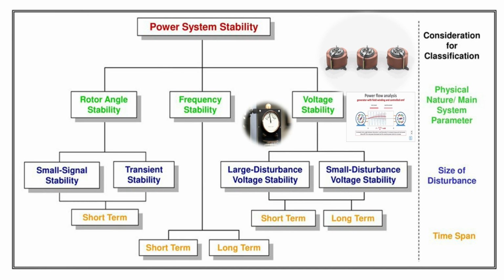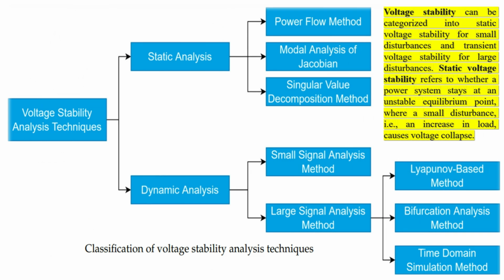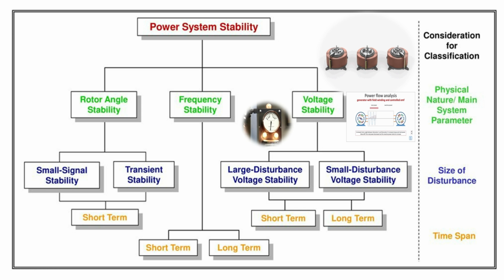Voltage stability can be categorized into static voltage stability for small disturbances and transient voltage stability for large disturbances. Static voltage stability refers to whether a power system stays at an unstable equilibrium point, or whether a small disturbance, i.e., an increase in load, causes voltage collapse. For traditional power systems, static voltage stability is determined by the active power transmission and the related voltage drop on the AC transmission line. However, for high VRE penetrated power systems, its static voltage stability mechanism has changed heavily. The key change is derived from the increasing penetration of power electronics, through which AC systems integrate VRE sources.